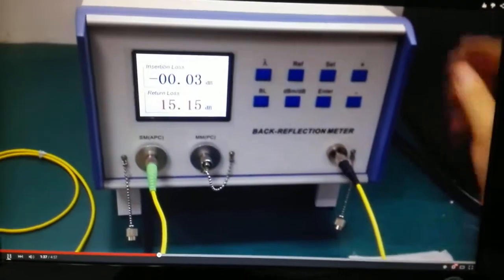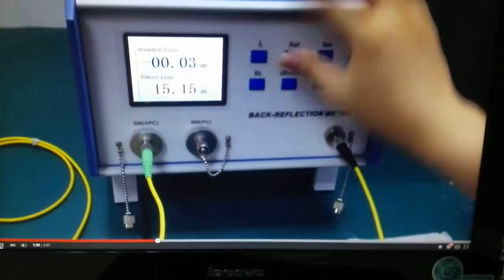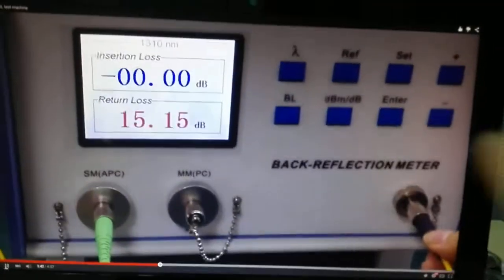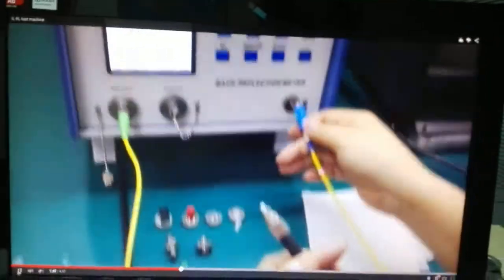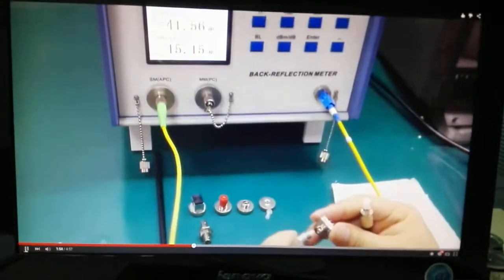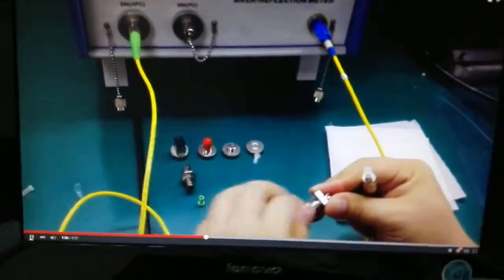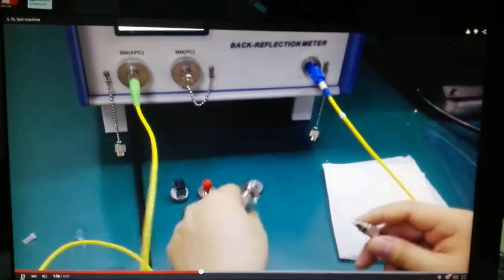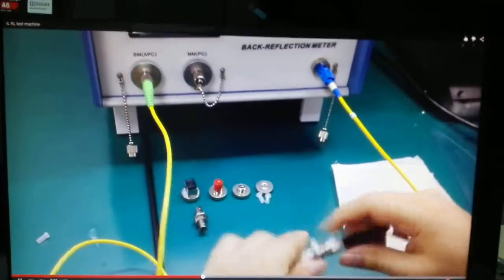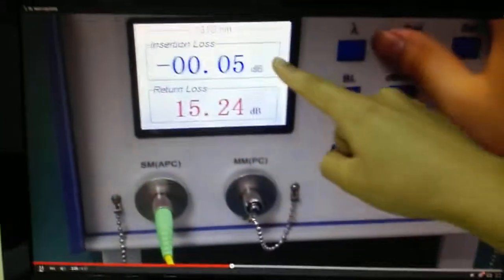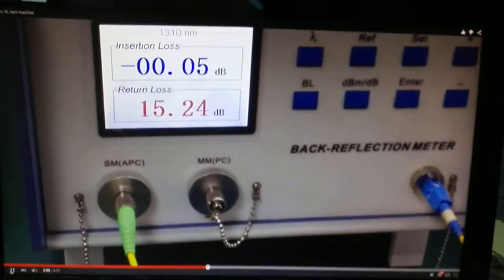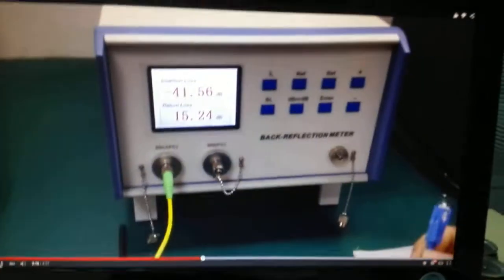First, you need to zero the calibration cable. How to zero? Just press the reference and make the data on the insertion loss 0.00. Okay, then test the cable you want to test. First, connect the two cables together by the adapters. And then you see the insertion loss shows 0.03. It is below 0.3. It is good data.